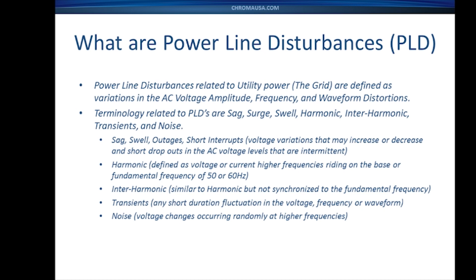Sag, swell, outages, and short interrupts all relate to voltage variations. Harmonics refer to a change in the wave shape where a higher frequency is riding on top of the base frequency, which is generally the 50 or 60 hertz fundamental frequency. Interharmonics are very similar, but they aren't synchronized necessarily to the base or fundamental frequency.